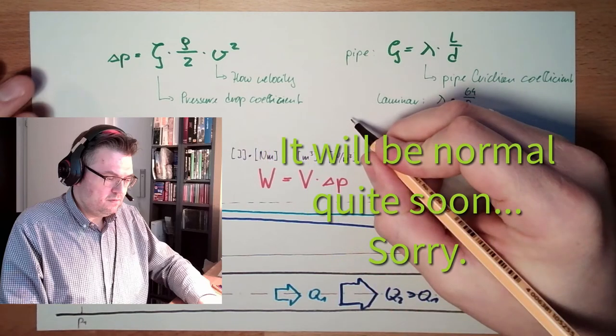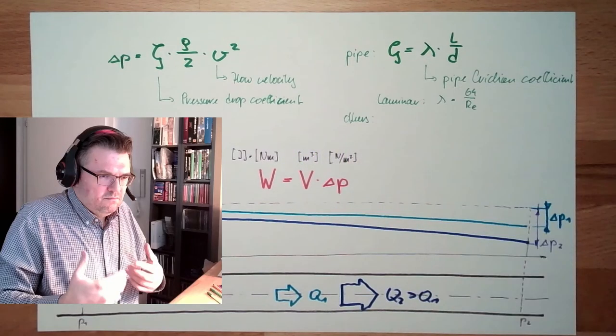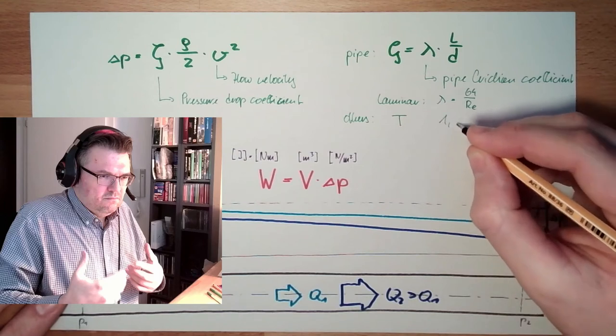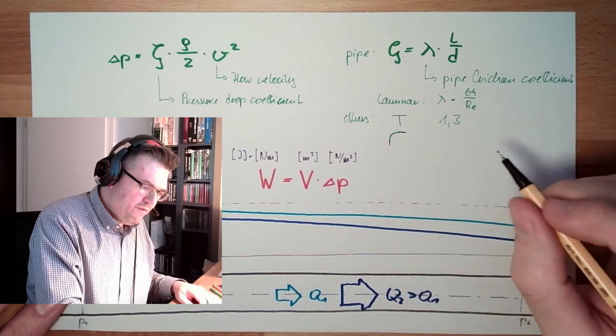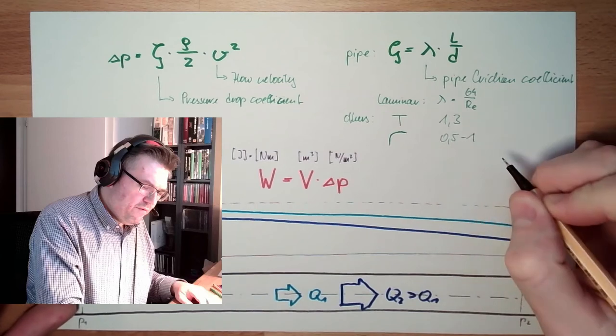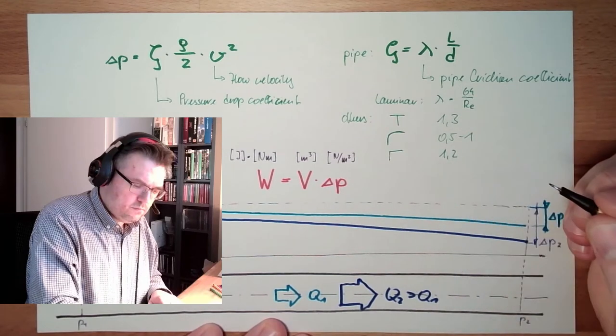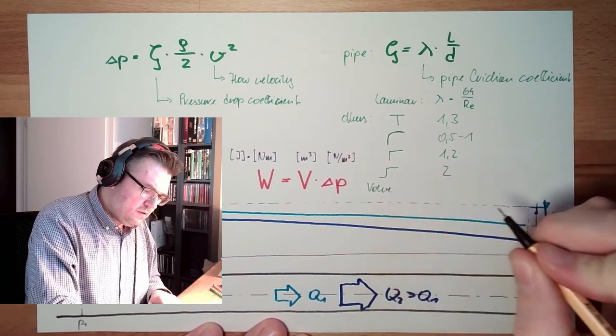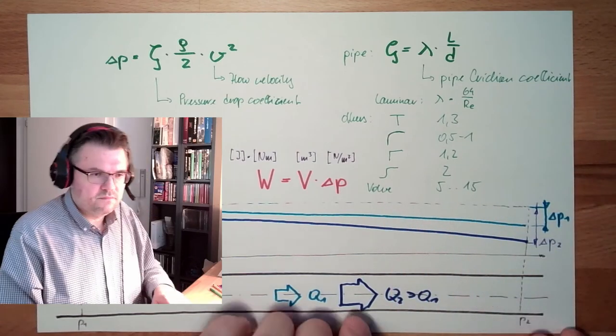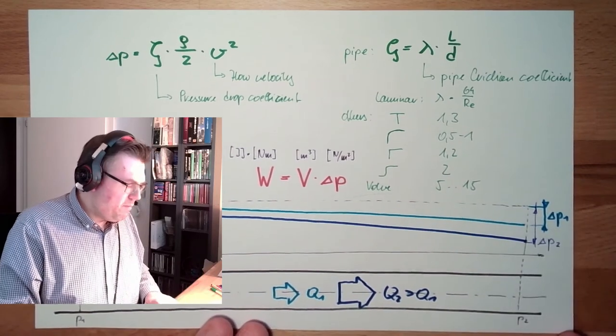So for all other things, this zeta is measured simply. If you have usual values, if you have a t-junction, zeta value is around 1.3. If you have a bend, 90 degree bend, then we are at 0.5 to 1. If you have a sharp 90 degree corner, then we are around 1.2. If we have a double change, we are at 2 somewhere. And valves, we are somewhere between 5 and 15, depending on which type of valve we are using. And these numbers are given by the manufacturer of these items.